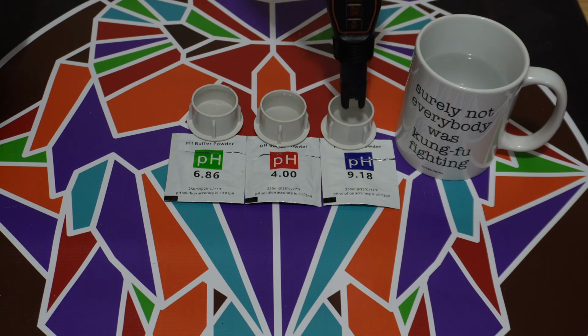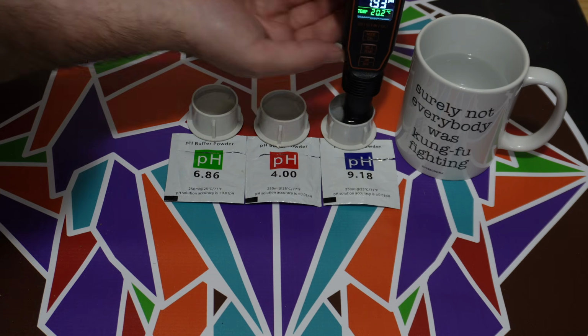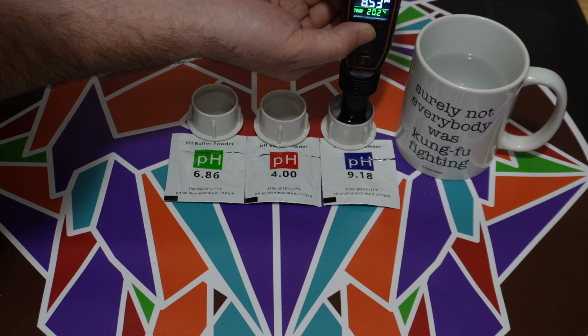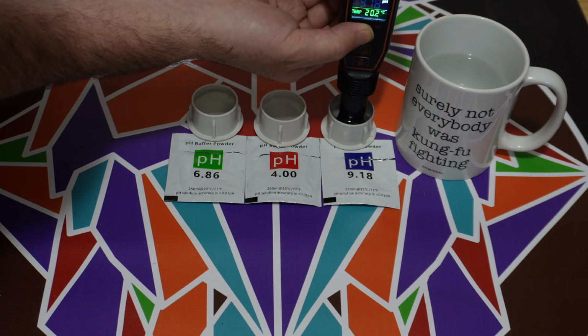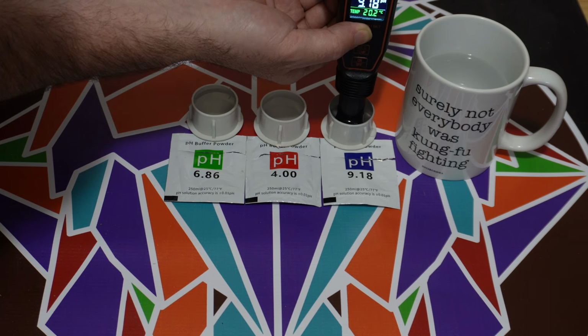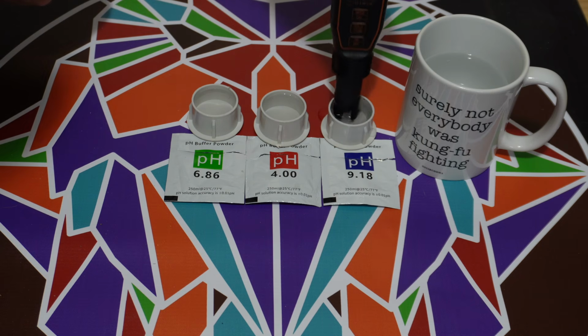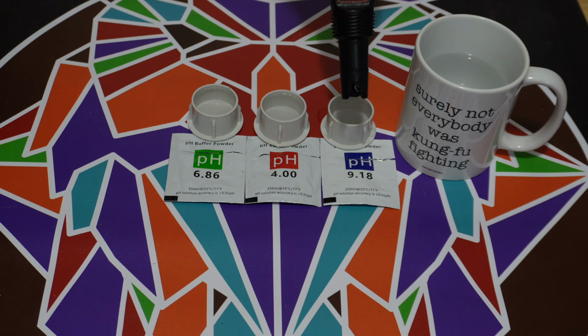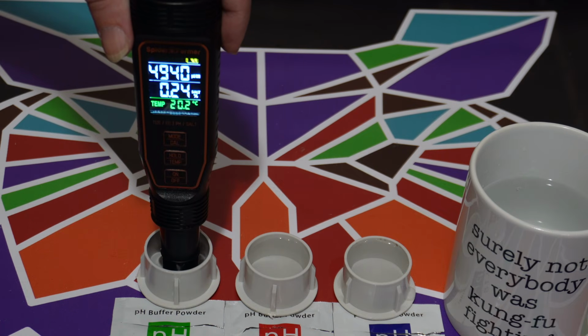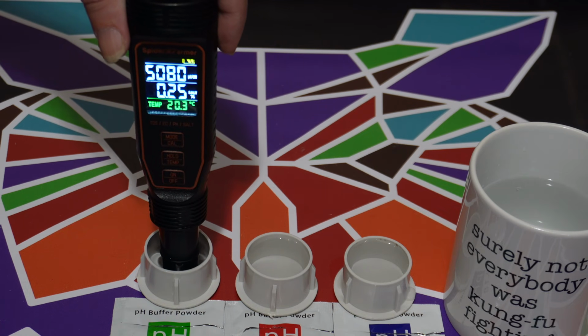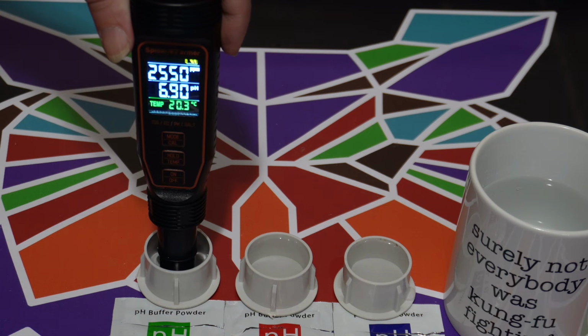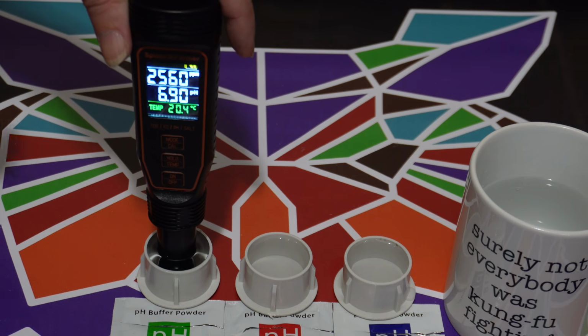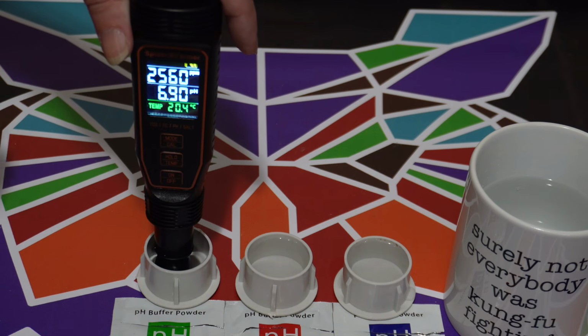All right, and then the third one, we go into the 9.18. We put that into the solution. We hold our button down again until it flashes that 9.18. There it is. We wait for that to go solid. And there we go. So this pen should now be calibrated. Putting it back into that 6.86 solution. Oh, wrong screen. Flip it over and then boom. It should be going right to around that 6.86. Sometimes it takes about 15-20 seconds before it narrows in on it.